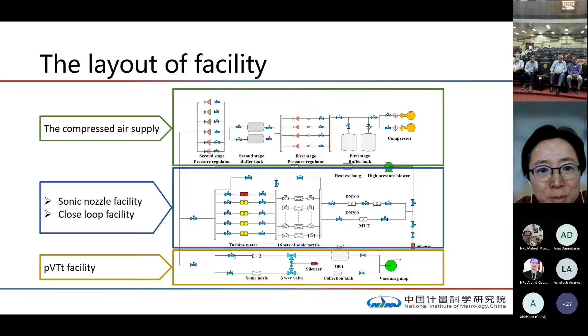The Pvtt facilities was located in the single room. The sonic nozzle and closed loop facilities were located in the same room. The Pvtt facilities is the primary standard in our institute, so the accuracy is important for us. The principle for Pvtt facility is very simple. The volume for the collection tank can be calibrated very well, so we can measure the pressure and the temperature very accurately for the collection tank.